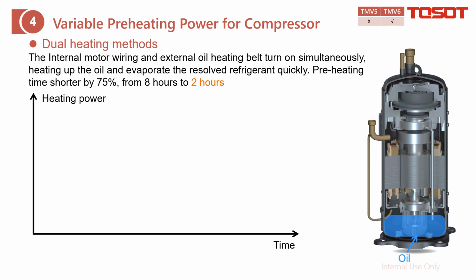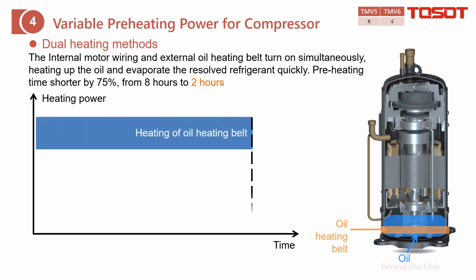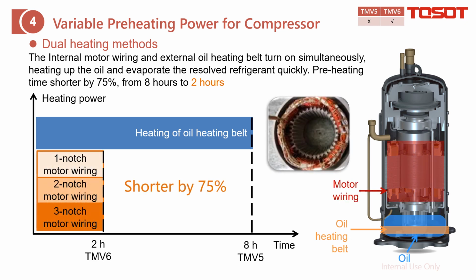For Gree 5, we just apply this oil heating belt, and of course, the power is not that high. It costs about 8 hours to ensure there is completely no problem. And for Gree 6, we apply this coil, which is just to rotate the compressor when it is running. But for this preheating, we just input the power or the current into it, just make it heat up, and then it will generate heat, which also heats up the oil. And with these two together, we can shorten the time by 75%, which only costs about 2 hours. Then we can finish this preheating.